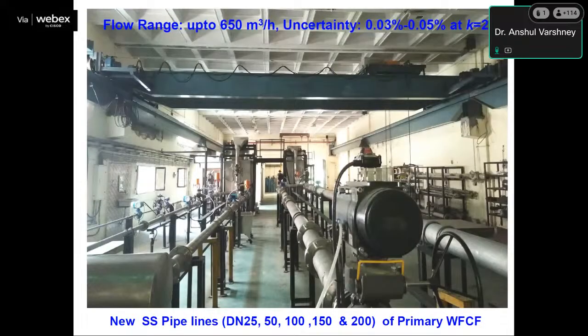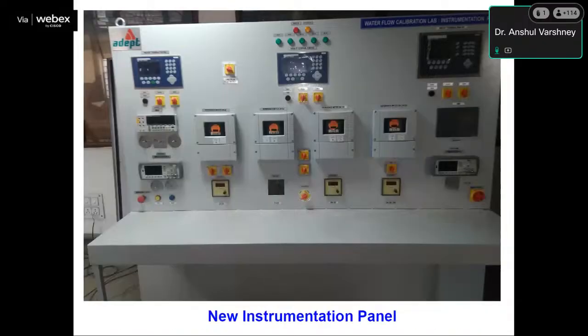This is the pictorial diagram for our water flow calibration facility. The range is up to 650 cubic meters per hour, and the uncertainty is 0.03% to 0.05%. This is the control panel. These are the displays for the weighing scales: 300 kg, 3000 kg, and 6000 kg. This is a 4 to 20 milliampere digital multimeter. This is a frequency counter, and these are the displays for different reference flow meters.